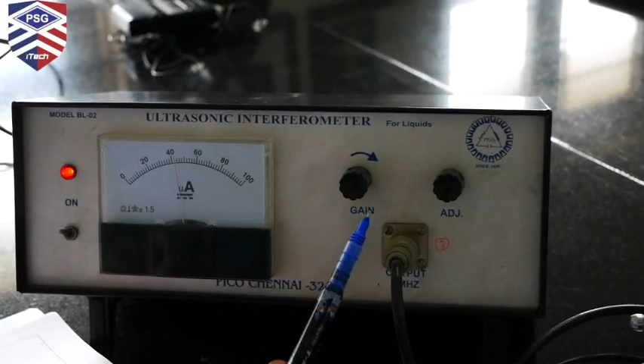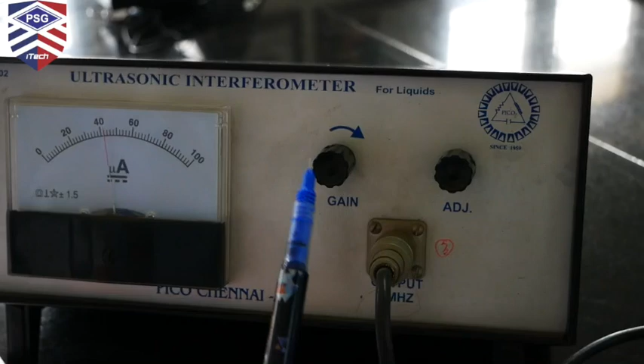So after having this reading, there are two knobs available in the RF generator. One is the gain knob, the other one is the adjust knob. The adjust knob is used to keep the needle within the scale, 0 to 100 microamperes. And the gain knob we use to increase the sensitivity of the microammeter. So now, having these two knobs, try to have the needle movement within the scale.